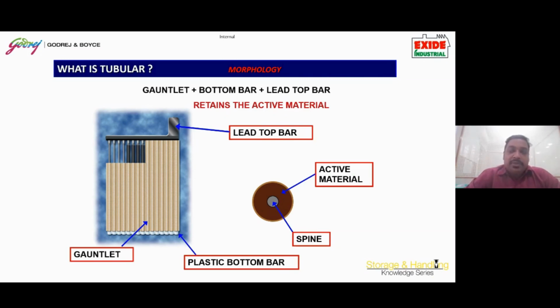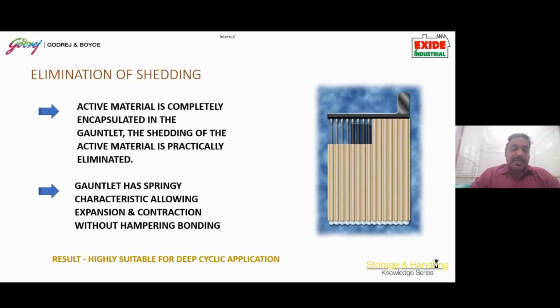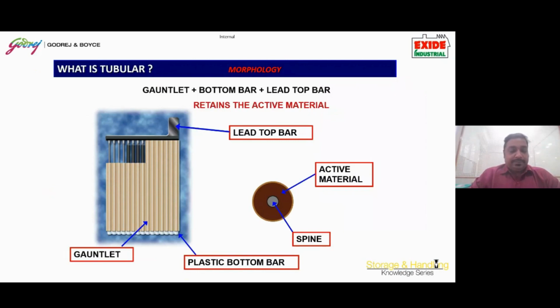If you ask why this cannot be used for starter applications, and why huge currents cannot be drawn from this kind of battery, the reason is that the gauntlet covers the positive active material. Hence the participation in the active chemical reaction rate is less compared to flat pasted batteries. That's why these batteries cannot discharge very high current over a short duration, but can discharge current for a prolonged duration consistently, getting recharged and repeating the same activity in subsequent cycles during its entire service life. Hence, we can say that all the traction batteries in the world have tubular positive plates. The negative plates, however, for any type of battery, remain flat pasted.